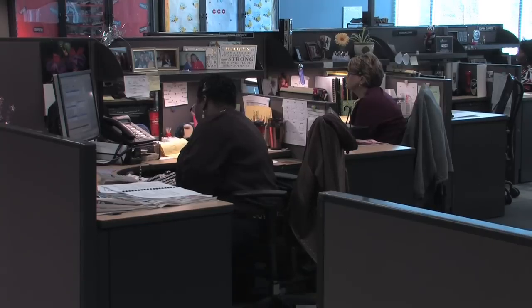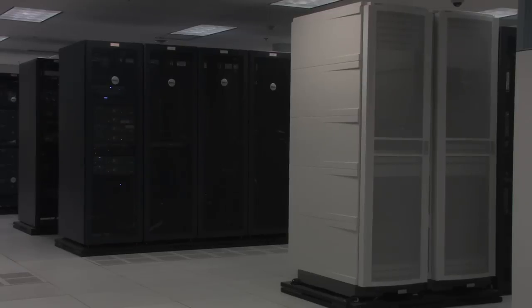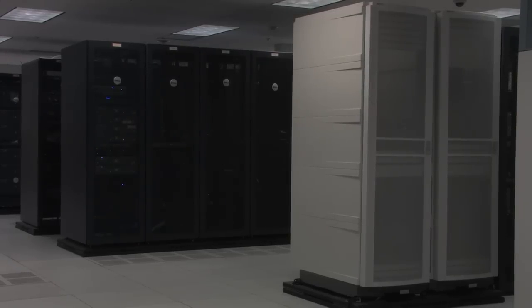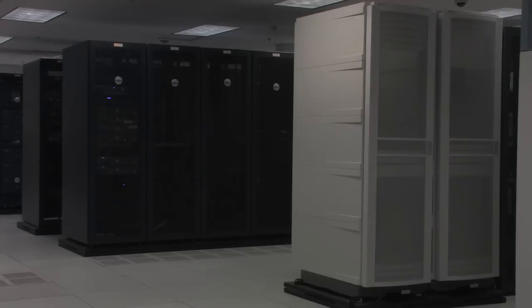For light, gas, and water, we always look to go above and beyond the code, because code normally only covers life safety issues. Typically, if you have an earthquake that will disable your building to the point where you can't occupy it, that's what you're looking to avoid in seismic code level design.